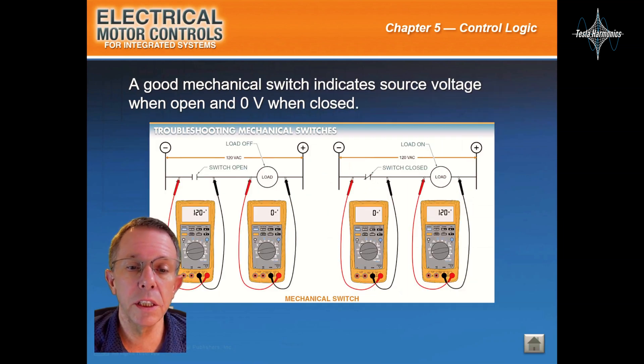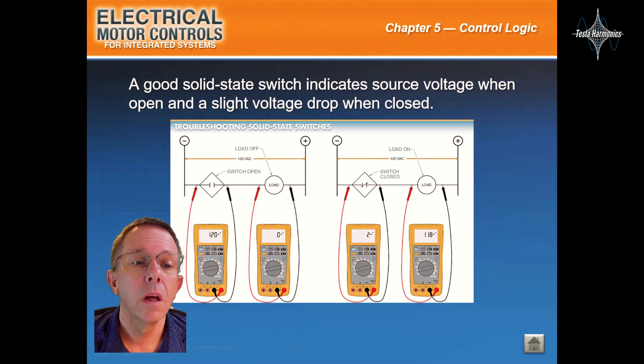A good mechanical switch indicates source voltage when open and zero volts when closed. A good solid state switch indicates source voltage when open and a slight voltage drop when closed.